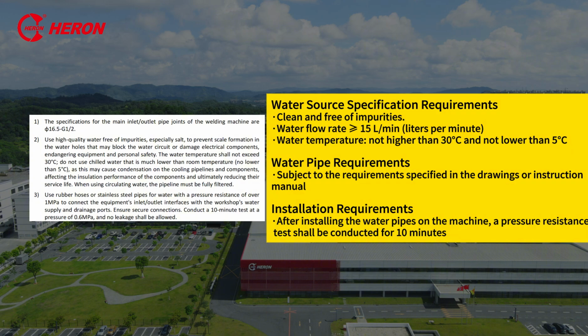Water source specification requirements: clean and free of impurities. Water flow rate is greater than or equal to 15 liters per minute. Water temperature, not higher than 30 degrees Celsius and not lower than 5 degrees Celsius. Water pipe requirements: subject to the requirements specified in the drawings or instruction manual. Installation requirements: after installing the water pipes on the machine, a pressure resistance test shall be conducted for 10 minutes.